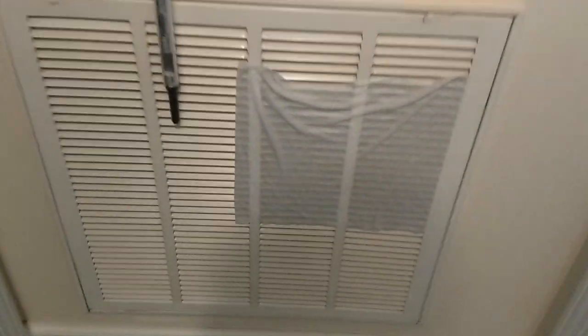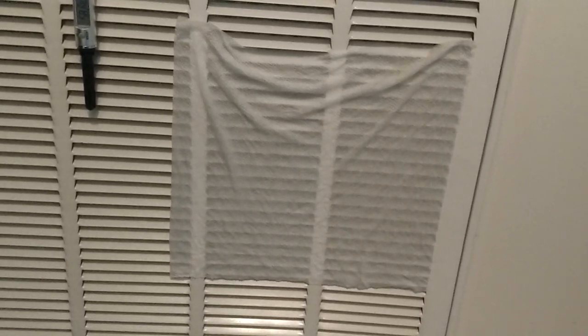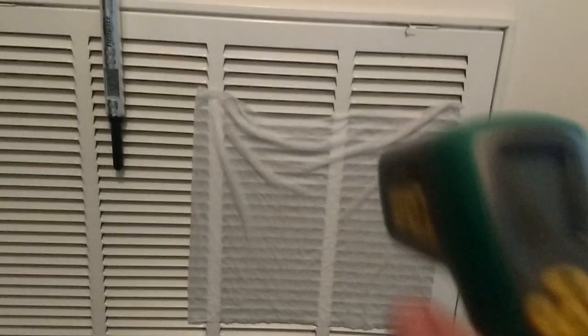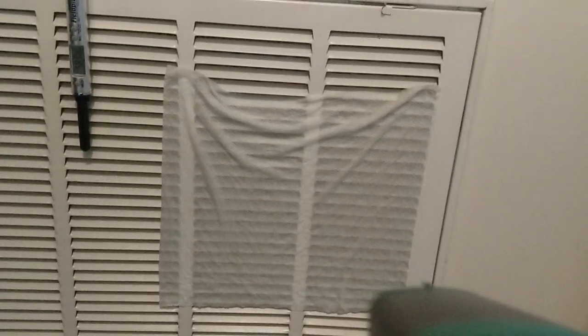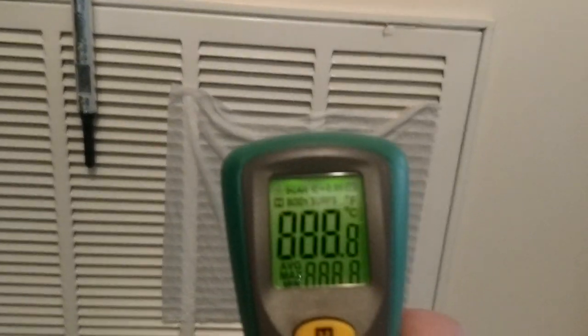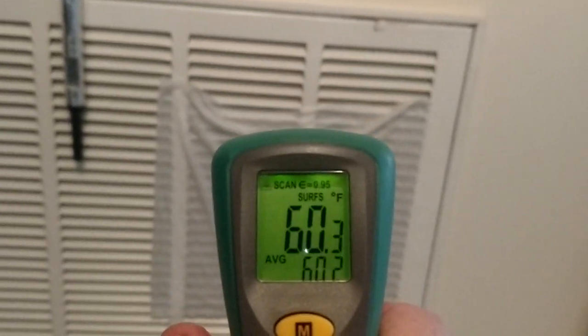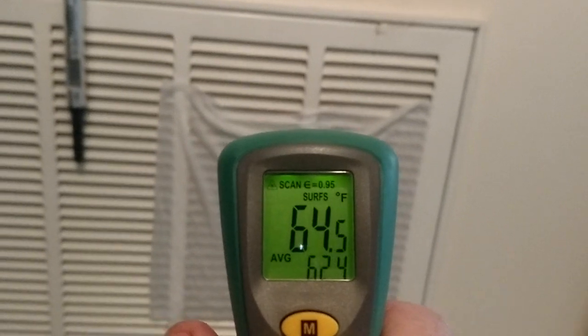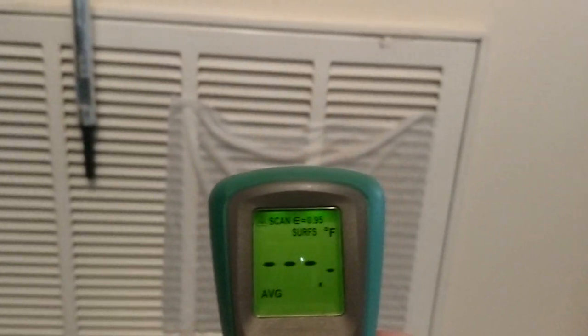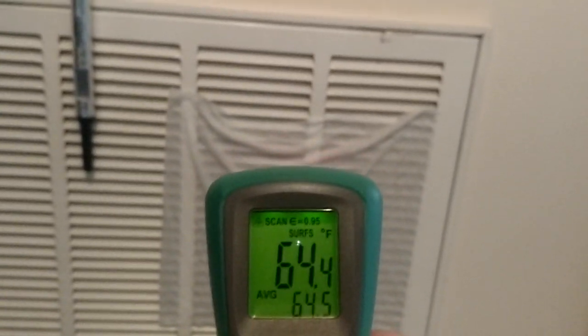In a pinch, if you don't have anything to get wet bulb, get a paper towel, wet it in the sink, wring it out until it's almost all the way wrung out - not really dripping but still wet. Throw it on the return for about 30 to 45 seconds or something like that.